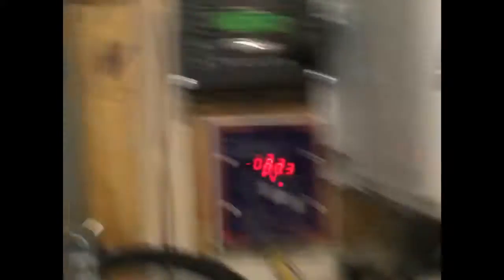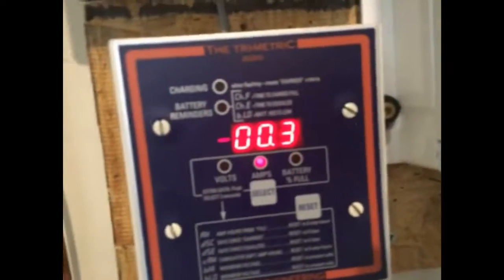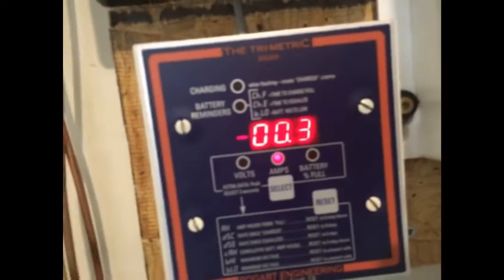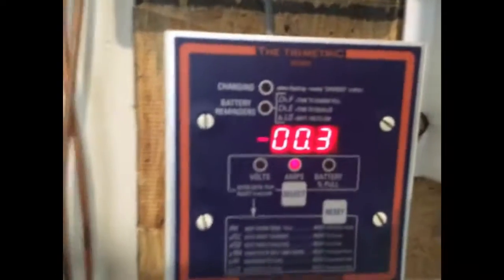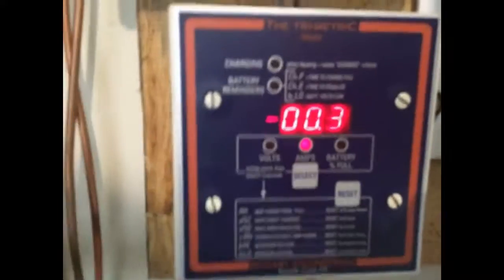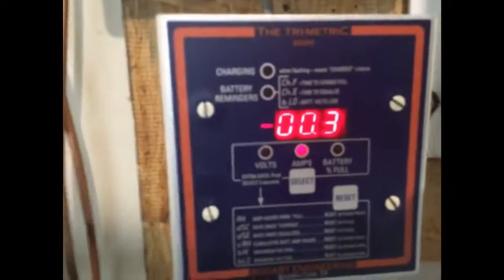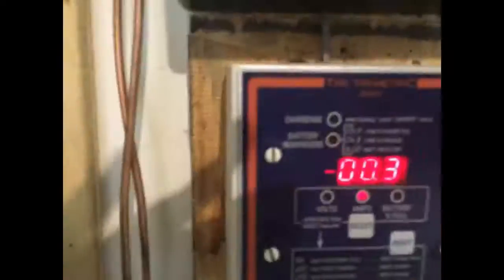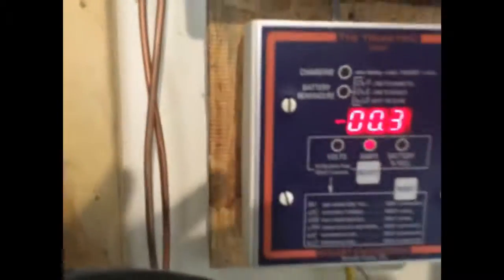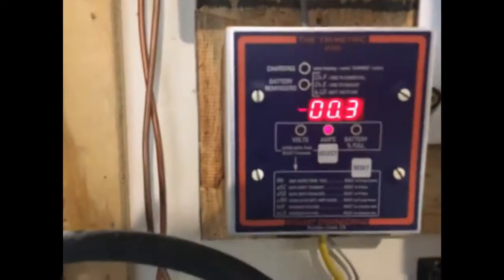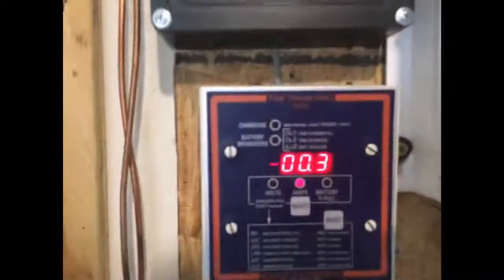The Magnum inverter actually pulls about 30 watts or so when in standby mode. This is just the inverter right here, just 0.3 amps. Yeah that's it, just 0.3 amps. So you can do your multiplications there and come up with how much it is, but it's 0.3 amps. And so right now it's telling me that your batteries are pretty low.